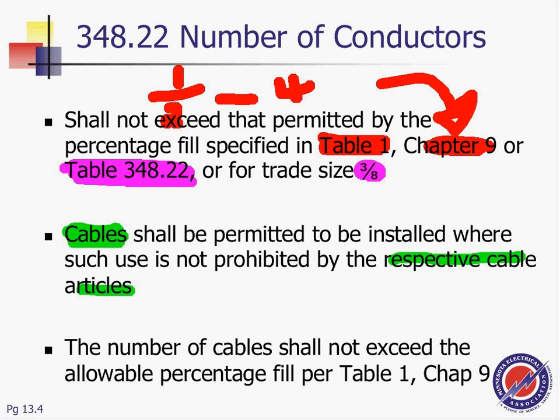So for example, can I put an MC cable? Ask me why I would do that. An MC cable in a flexible metallic conduit? Yes, no problem. In flexible metal conduit, you can put an MC cable. Why would you? A different story. So basically, can I use a 100 kcmil THHN cable? Yeah, no problem.